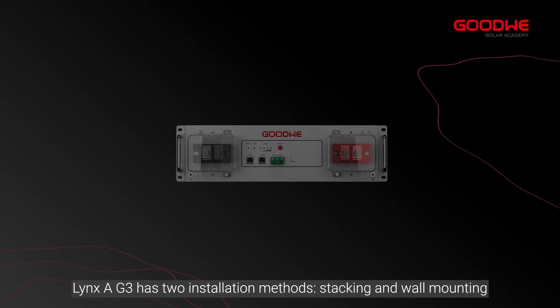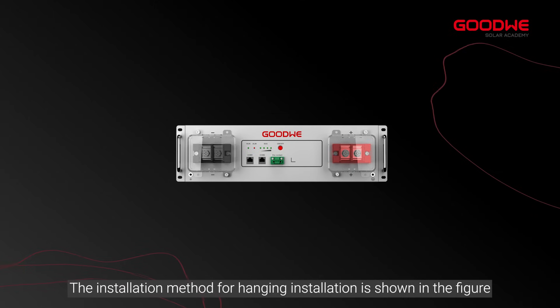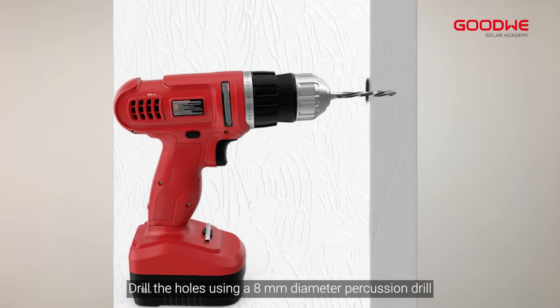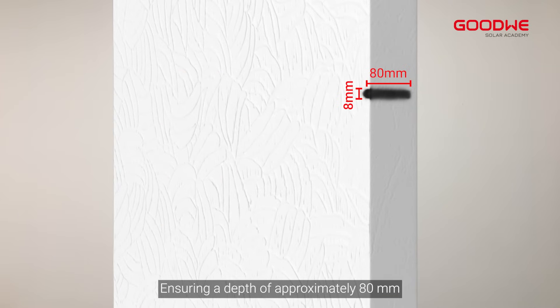The Lynx A G3 has two installation methods: stacking and wall mounting. The installation method for wall mounting is shown in the figure. Take out the triangular bracket and drill the holes using an 8 millimeter diameter percussion drill, ensuring a depth of approximately 80 millimeters.